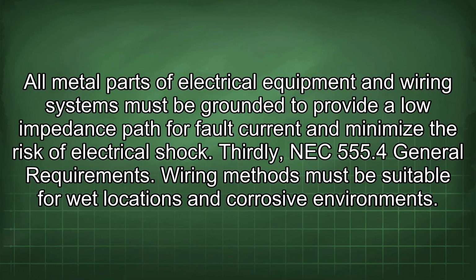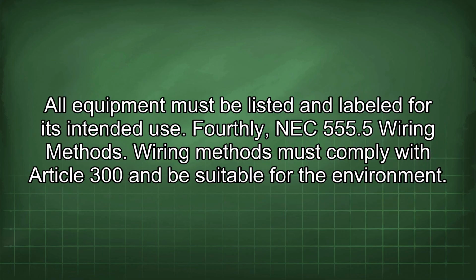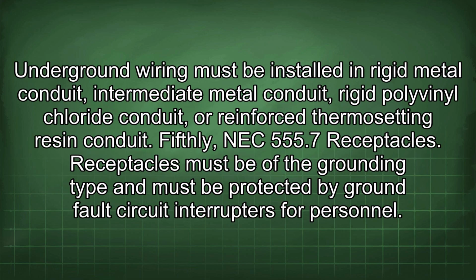Thirdly, NEC 555.4 General Requirements. Wiring methods must be suitable for wet locations and corrosive environments. All equipment must be listed and labeled for its intended use. Fourthly, NEC 555.5 Wiring Methods. Wiring methods must comply with Article 300 and be suitable for the environment. Underground wiring must be installed in rigid metal conduit, intermediate metal conduit, rigid polyvinyl chloride conduit, or reinforced thermosetting resin conduit.